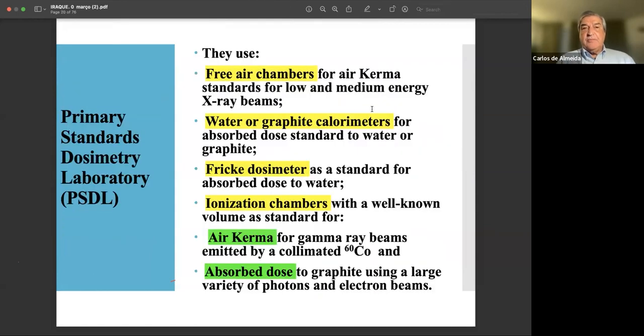Now, the primary standard dosimetry lab, what do they use? They use free air chambers for air kerma standards for low and medium energy X-ray beams, from 30 kV to 400 kV. They use different chambers depending on the range you have to measure; the size of the chamber is different. They use water calorimeter or graphite calorimeter for absorbed dose standards to water or to graphite, and then you have to convert from the graphite to water. They use the Fricke dosimeter as the standard for absorbed dose to water, which is a chemical dosimeter. Ionization chambers that require a well-known volume are used as a standard, for instance, for air kerma when you use gamma rays emitted from cobalt-60, or even for absorbed dose to graphite, which you can use for a large variety of photon and electron beams. Next slide.